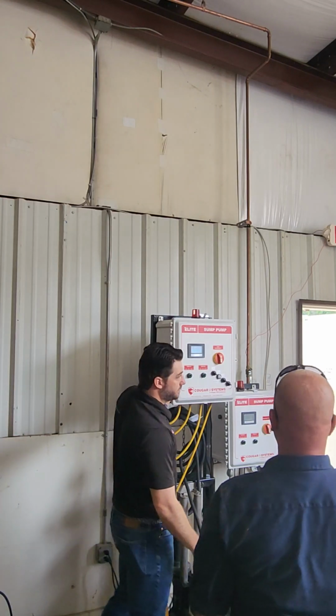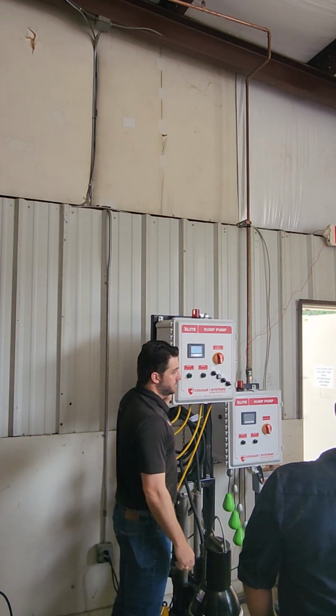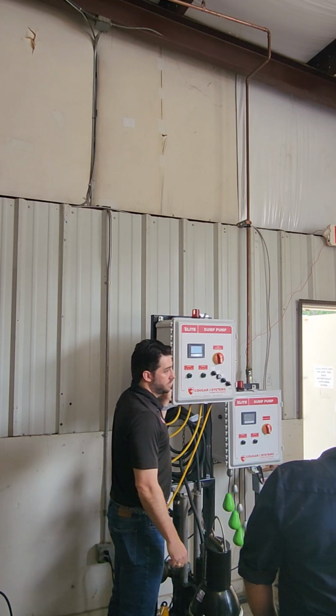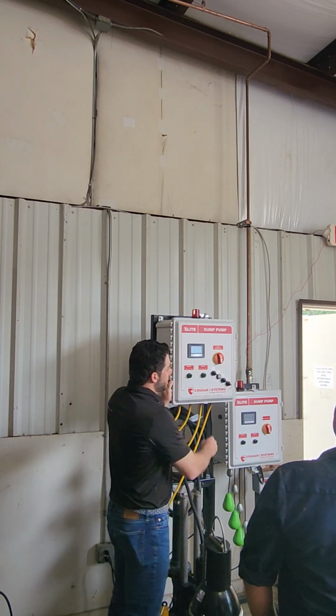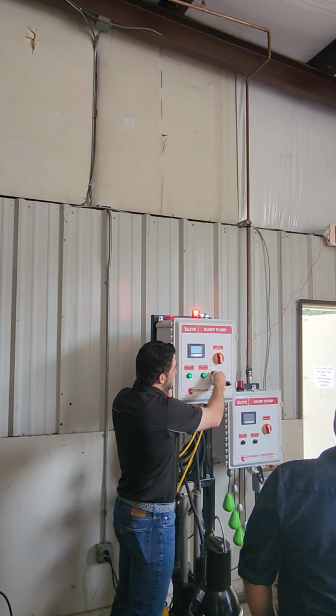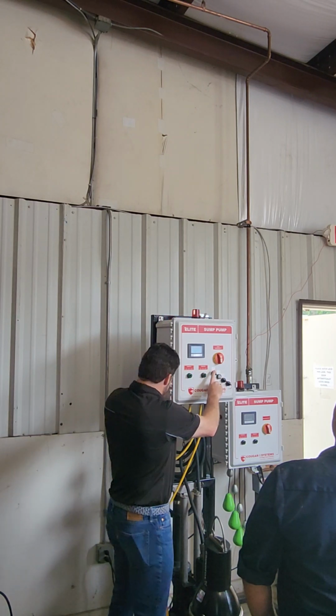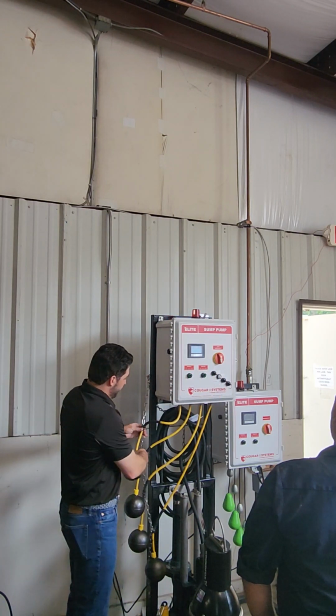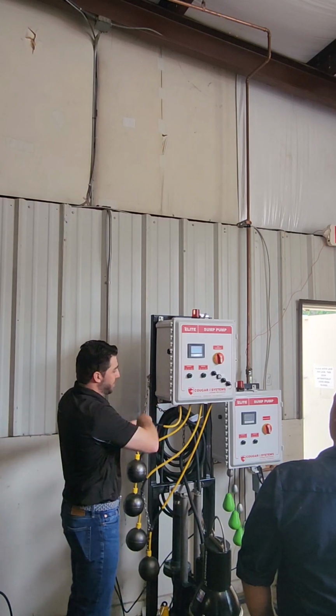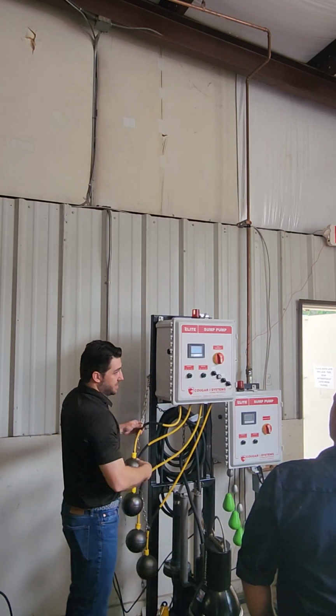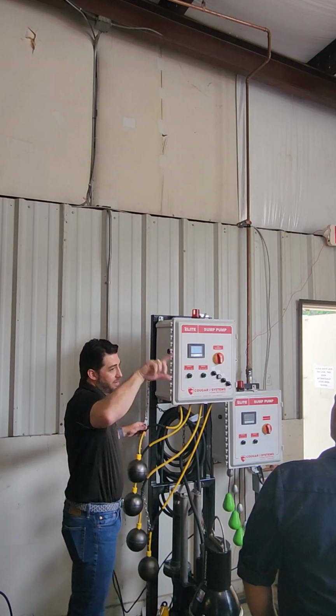Really? So if your first float fails, you turn on both, you get a high alarm, and then the water starts coming down, when does it shut off? So on the high level, if it's just running off the high level alarm, it's the pivot point of this top float switch that's going to determine the pump down range. So every time it's going to sit there and just high level, right?